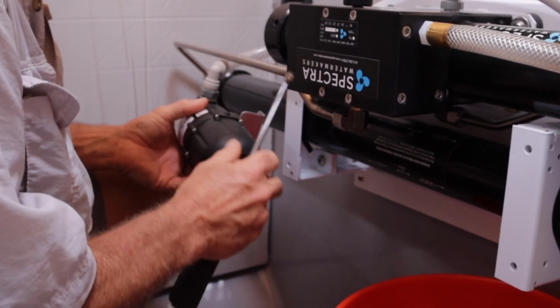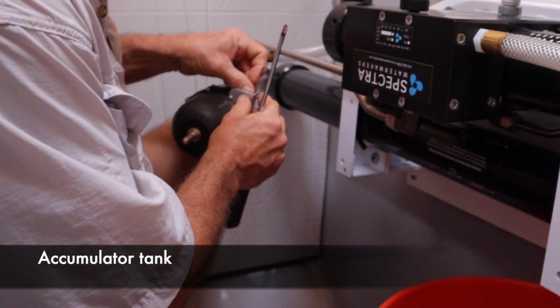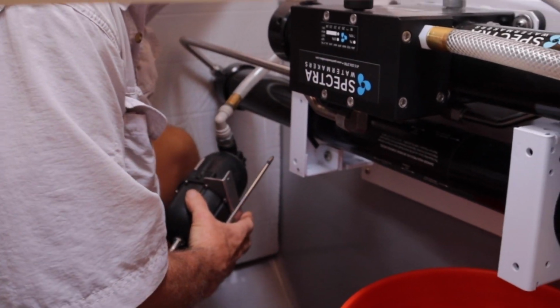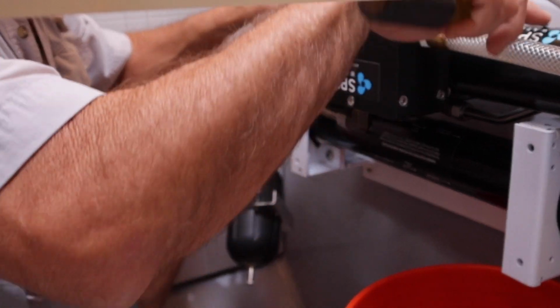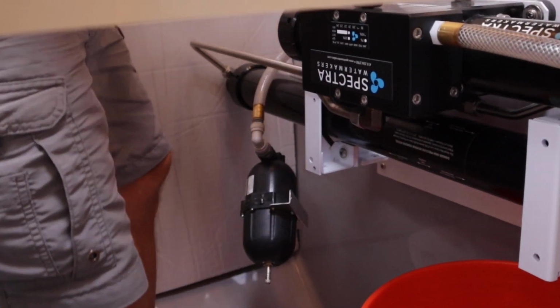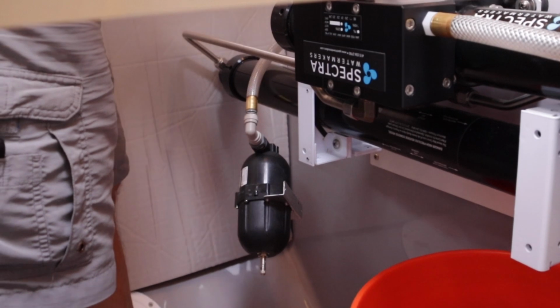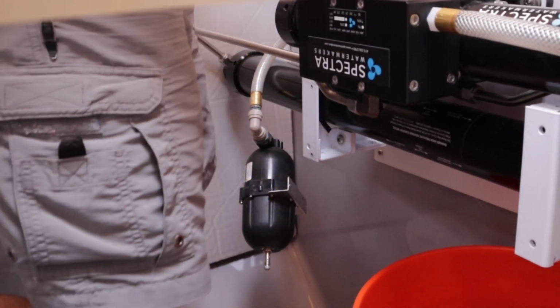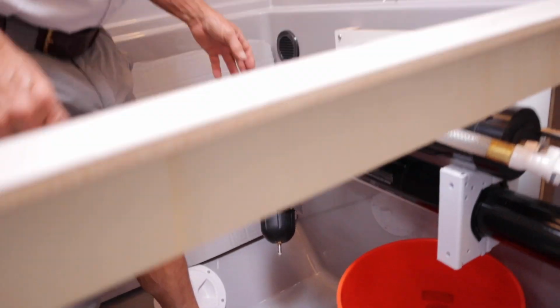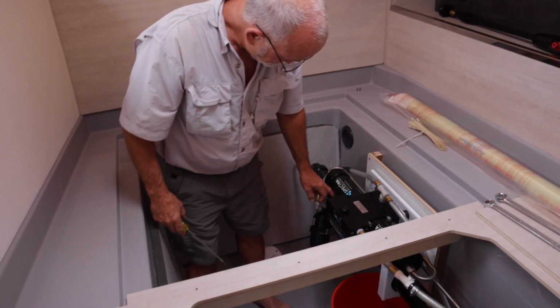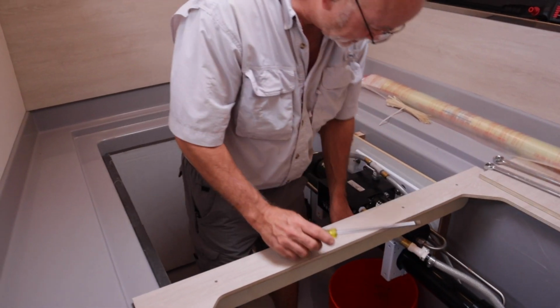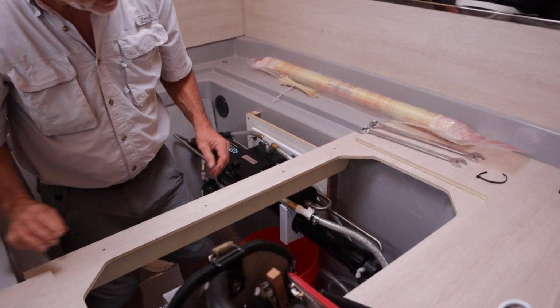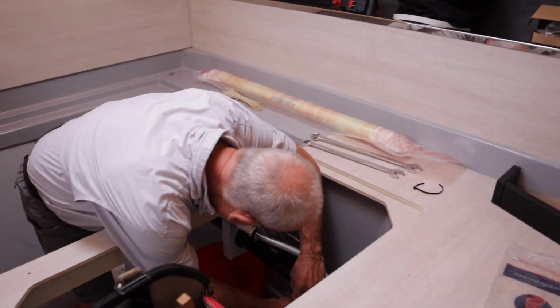This is the accumulator tank. And the purpose of this is that this pump has two cylinders. When it shifts back and forth, the cylinders go back like that. When it hits and stops and reverses, it creates a bit of a plumbing hammer. And that's just to soften that blow. But I need to get to this bracket right here. So these two brackets will come off, and then the membrane vessel will drop right off. Here's where we're starting to get a little bit wet.